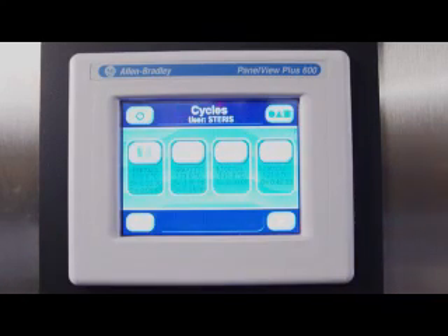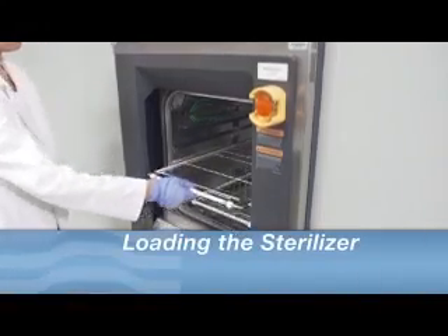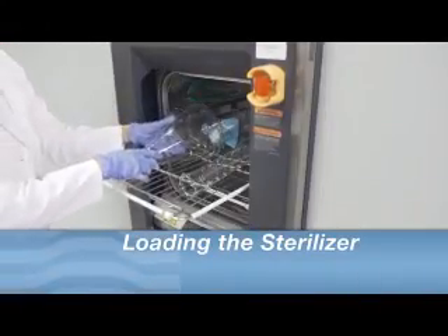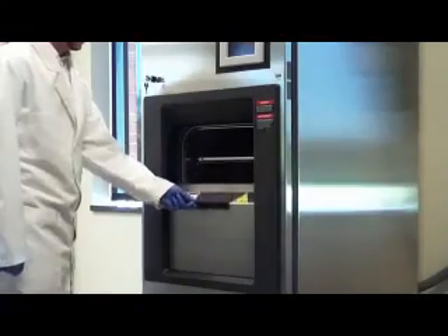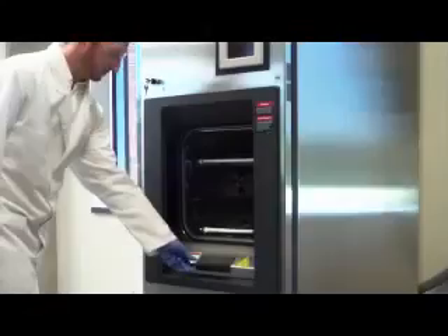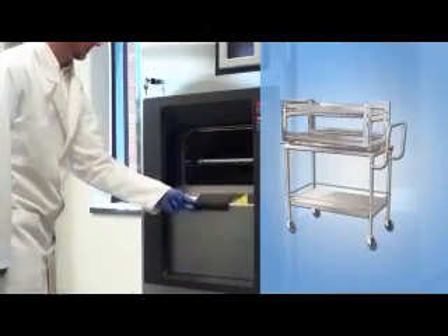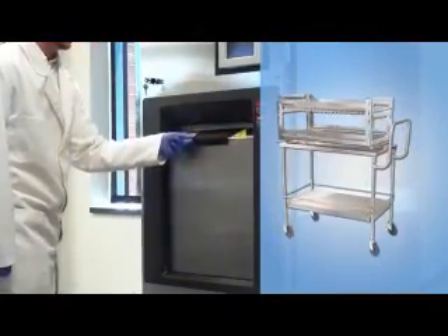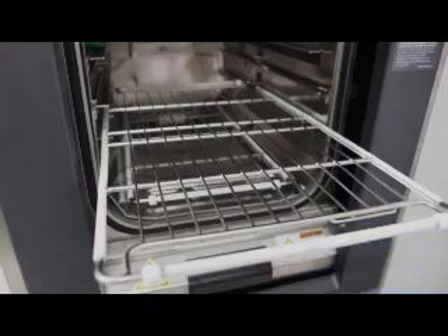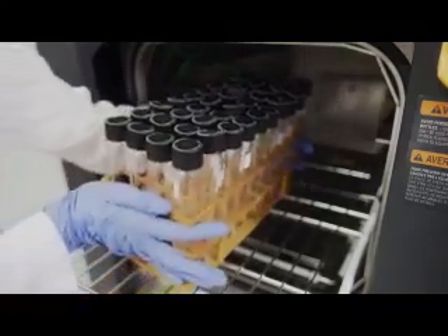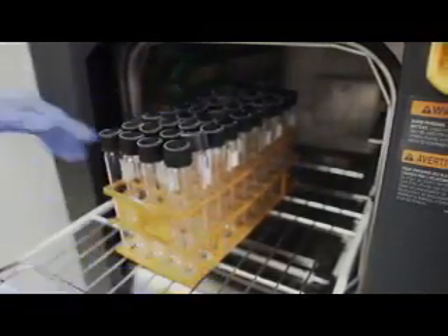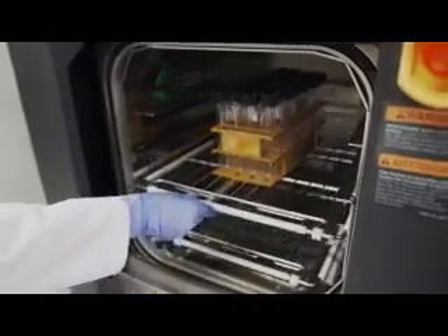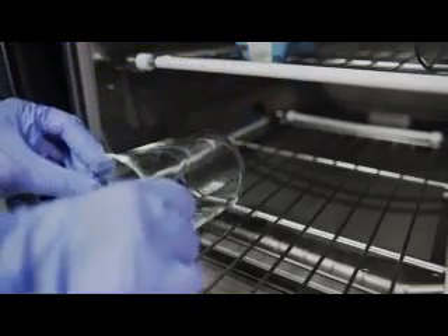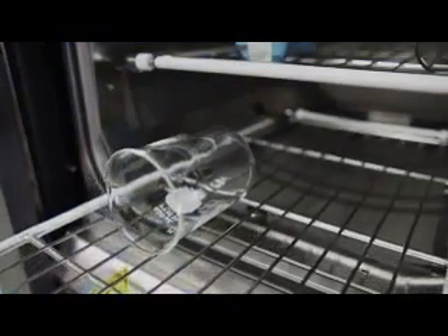The AMSCO Lab 110 is equipped with a rack system that holds 2 removable shelves. The Lab 250 is loaded using either a rack and shelf system or a loading car and carriage. The shelves can be pulled out halfway and lock in place, allowing for ease of loading. As you prepare your load, remember to look for areas where air might be trapped and ensure that steam is able to contact all areas.